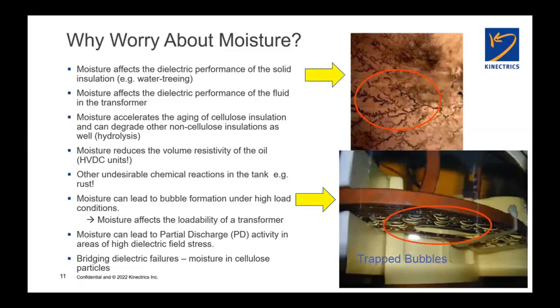Another thing that's quite obvious is undesirable chemical reactions that can be occurring in the tank. And the obvious manifestation of that is rust. So if you ever open up a transformer and see rust on the inside of the tank, if it's not painted, on the core clamps, on the edges of the core steel, etc., that's a clear indication that we have a moisture problem inside the transformer, because in a properly dried transformer, there is not enough moisture to lead to oxidation of steel that causes rust.